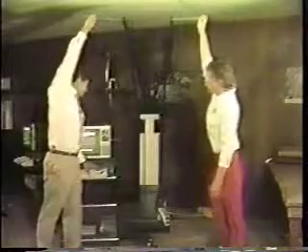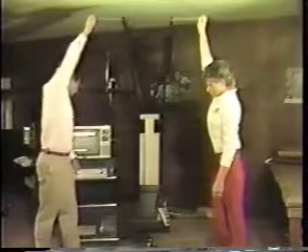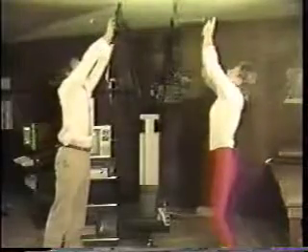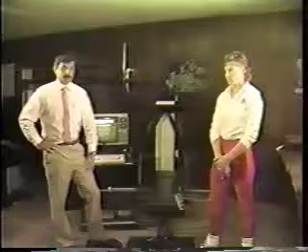And now we repeat the procedure with 90 pounds of weight. Step back. That now completes the full calibration procedure, which takes approximately 5 minutes. This procedure is done on a daily, weekly, or monthly basis, depending upon the needs of the particular investigator.